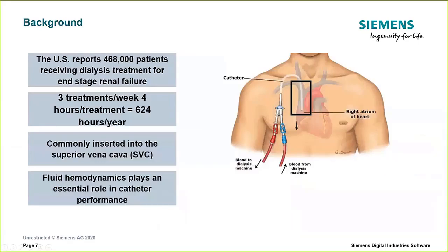We've chosen an illustrative example to put these ideas in concrete form: predicting the performance of a hemodialysis catheter using CFD. These catheters are inserted into the superior vena cava — the main vein entering the heart — for filtering blood to remove waste when a patient's kidneys are nonfunctional. The catheter has two lumens: the arterial side, which takes blood to a dialysis machine for filtering, and the venous side, which returns clean blood to the vena cava. The procedure is critical and hemodynamics plays an essential role.